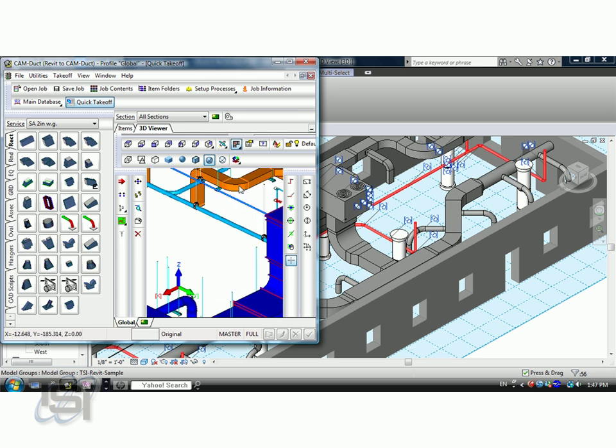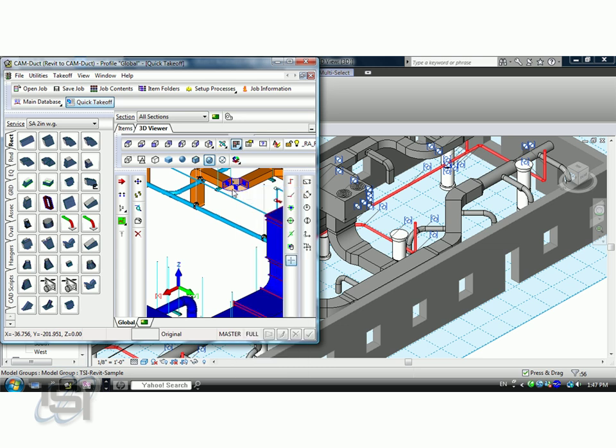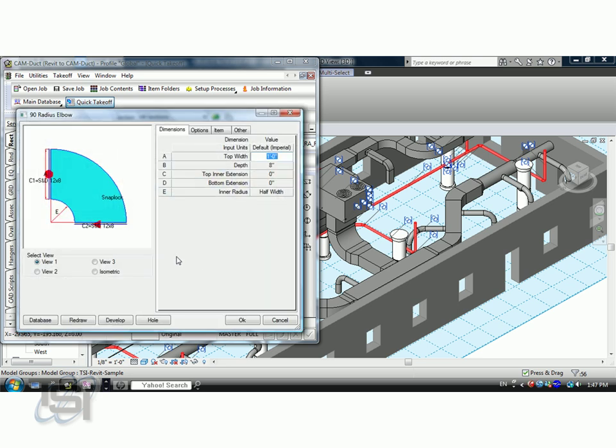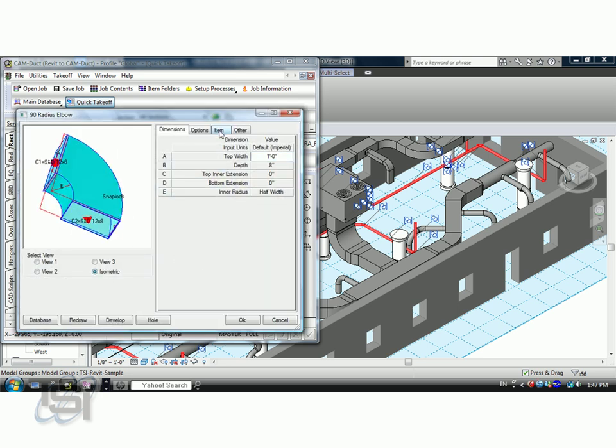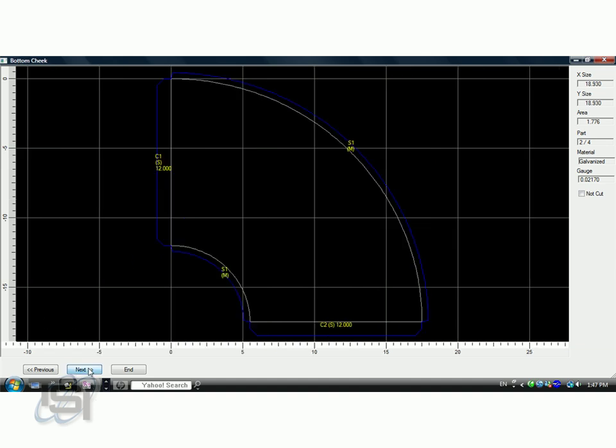Now, each one of these components right here is also hooked to our estimating system. If I right click on that right there and see the best way to do this is to show the manufacturing. Here's our component. It's using the pressure class of 2 inch water gauge to manufacture that. Here's the development of the pattern. Bottom cheek, throat wrap, back wrap.